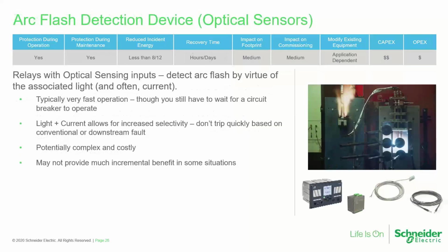Optical sensing, we're giving some guidance on energy reduction, reduced incident energy. Notice here it says less than 8 calorie, 12 calorie range. Why is it not any lower than that? Because these optical arc flash sensing devices operate very quickly. The relays, typically they may send a trip signal in as little as 2 milliseconds after an arcing fault occurs.